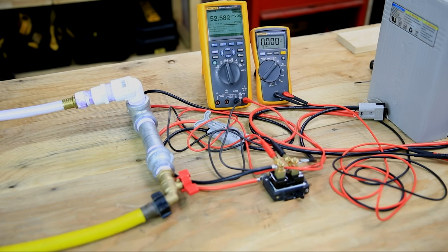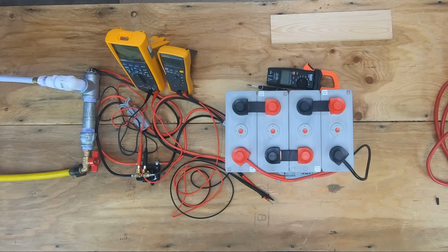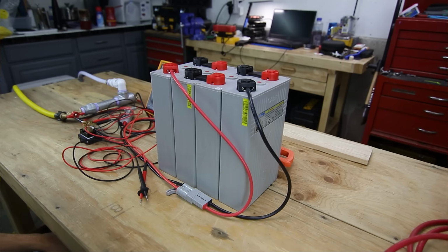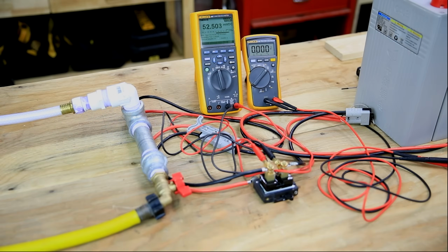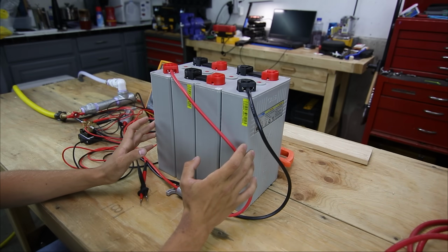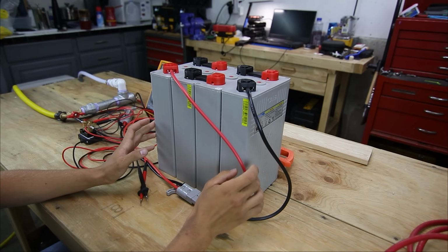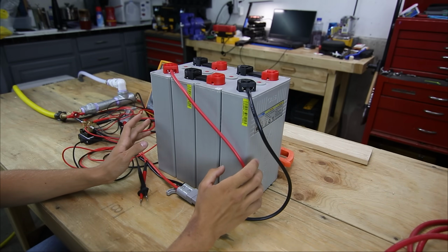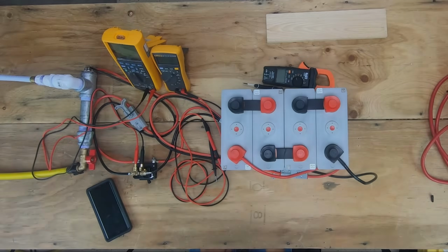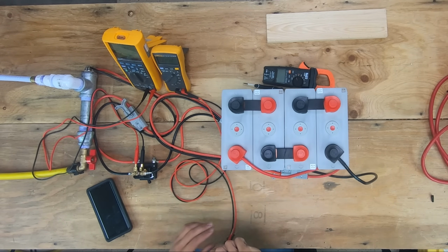I'm going to let this run its course with the Fluke 287, continuing to log the data. Now I need to wait around, because at 52 amps, if you figure these batteries are right around 200 amp hours, this test is going to take 4 hours. So I need to find something to do while I carefully monitor this, since there's no BMS on here to shut the test off when the batteries are empty. I'm going to stop the test at 3 volts. Okay, so this test is underway quite a bit.